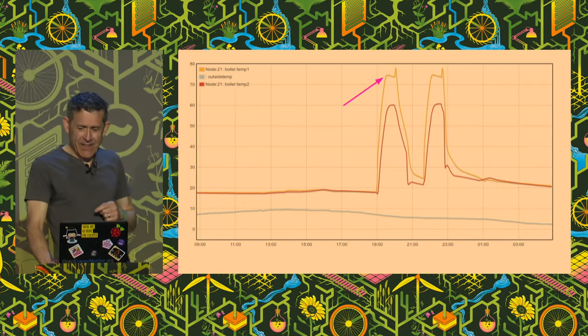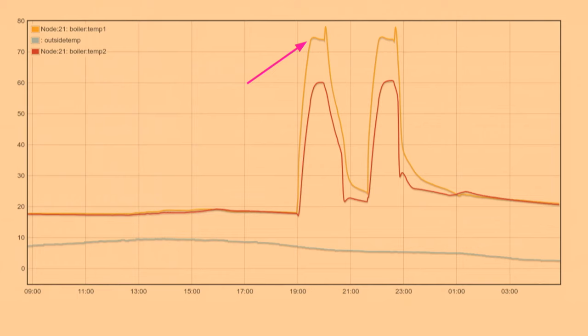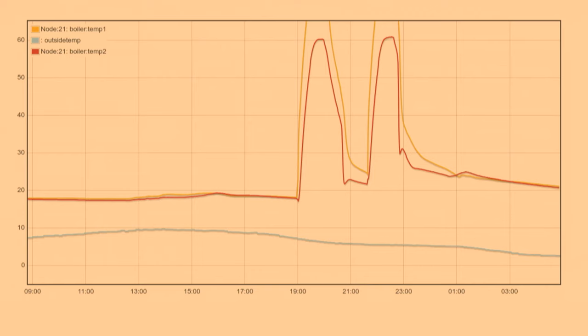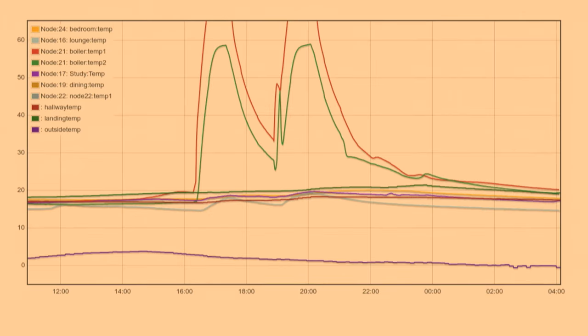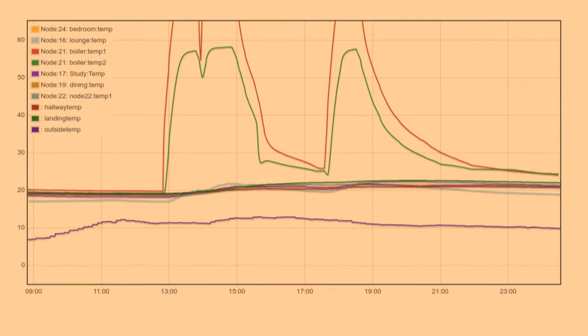Here's another two hours of heating — 7 to 8 and 9:45 to 10:45. Things get even worse: on the second lump of heating, the temperature rises even quicker and sits with the flow temperature at 75°C and the return temperatures over 60°C, which just goes to prove how rubbish it all is. This is the same graph just stretched out so you can see how things change.